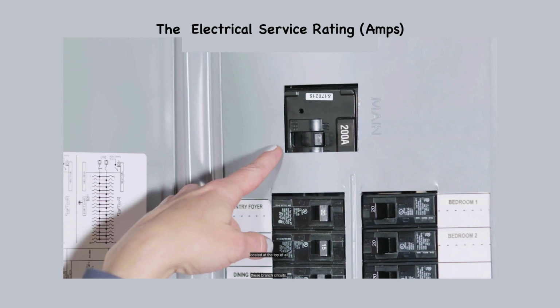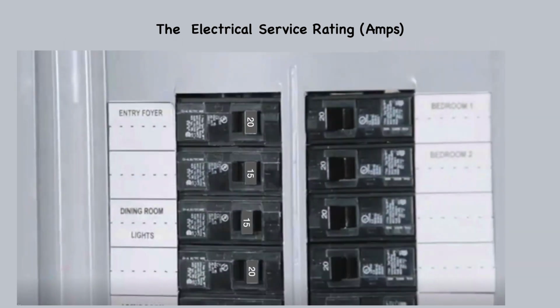It is rated for 100, 150, 200 or even could be 400 amps, and it's always 240 volts. Before you start work on any circuit throughout the house, make sure you shut off the power here at the breaker box. The individual branch circuit breakers cut off power to each individual circuit. They are rated for 15 or 20 amps. Amperage is the capacity of the circuit, and determines how much power the circuit can handle before the breaker trips.